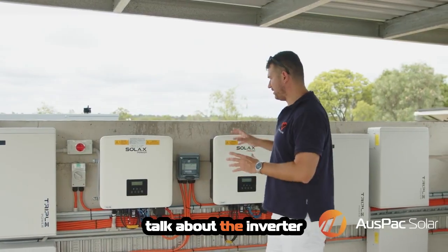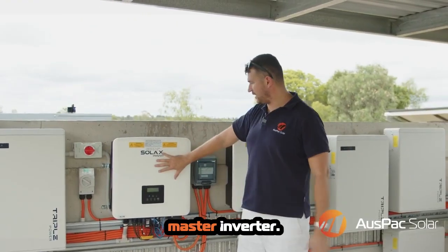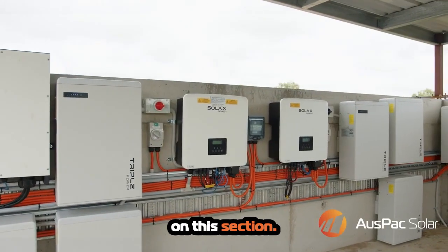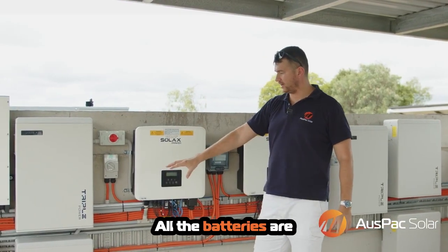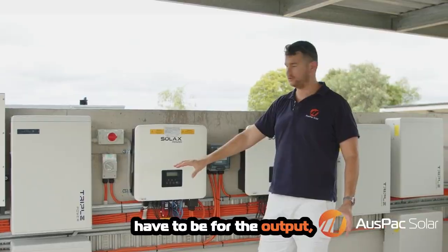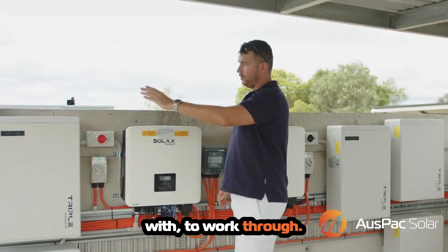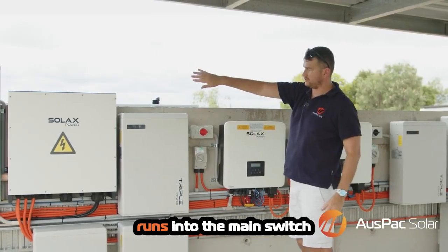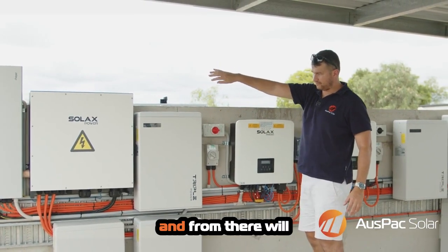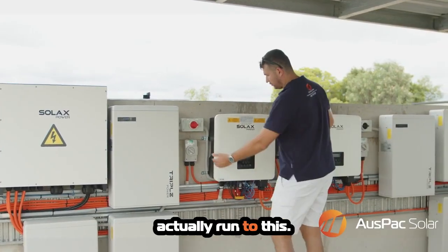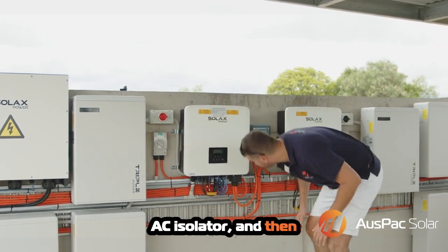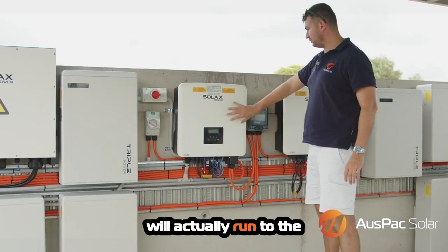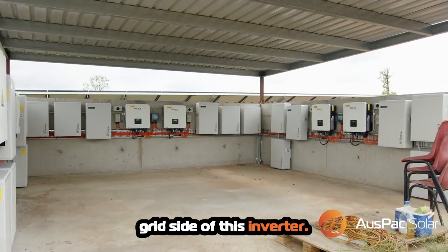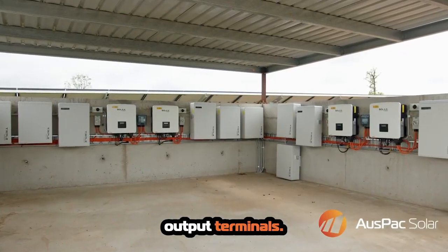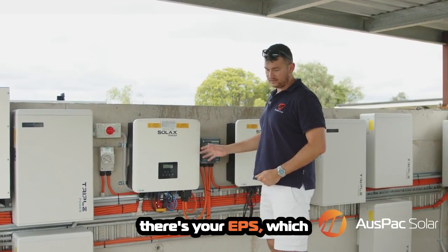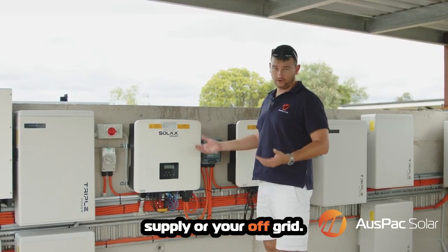So now we're going to talk about the inverter and the batteries. This here is the master inverter. I'm just going to focus on this section. There is one master inverter. All the batteries are identical, which they have to be for the output. The wiring, to start with, we have the genset that runs into the main switch of that switchboard, and from there we'll run to this AC isolator, and then from that AC isolator we'll run to the grid side of this inverter. Okay, so there's two output terminals. There's the grid terminals, and then there's your EPS, which is emergency power supply, or your off-grid terminals.